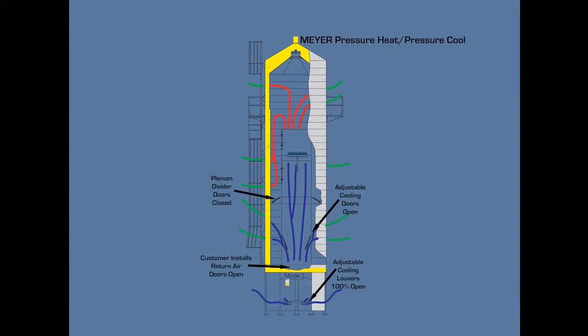This drying mode uses fresh air drawn through the dryer's air inlet louvers by the double wide double inlet fans. The air then passes through the full flame wall burner, mixing the fresh air and the heated air as it is pushed into the tower's heat plenum and through the grain columns before being exhausted.